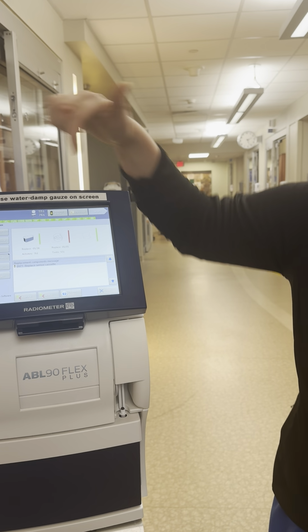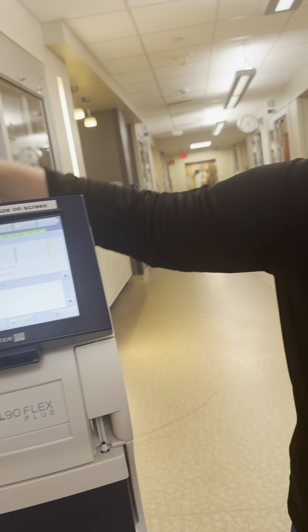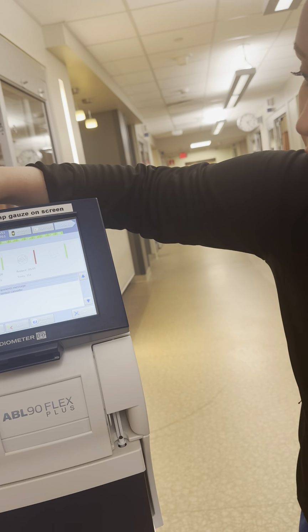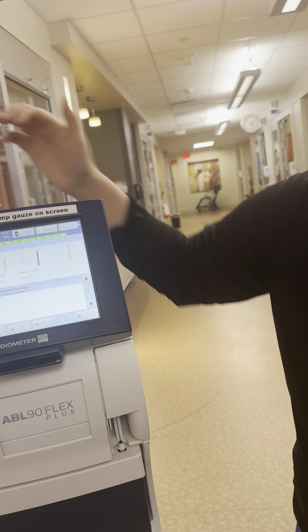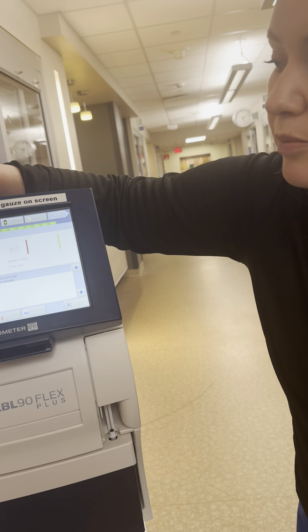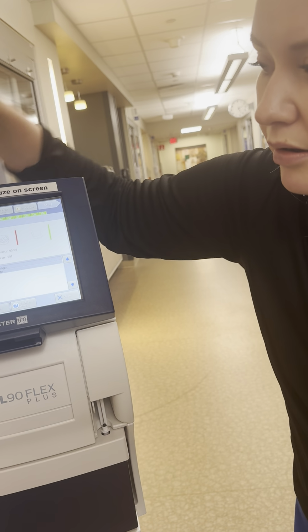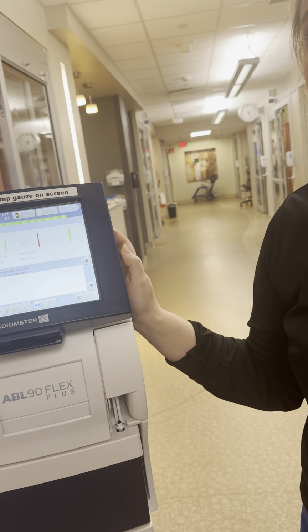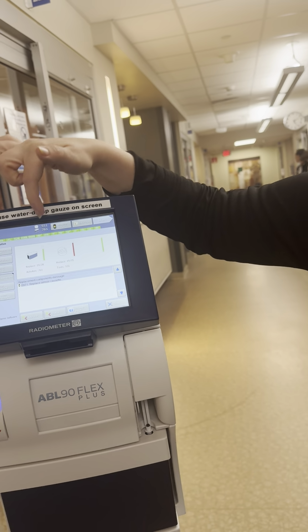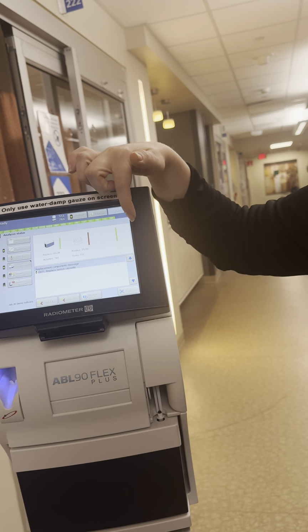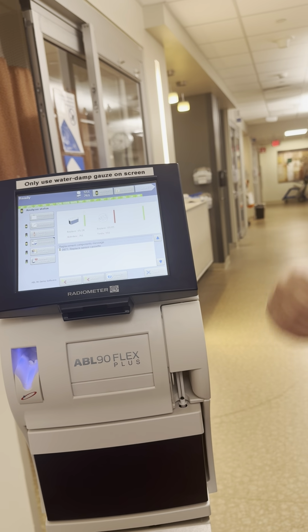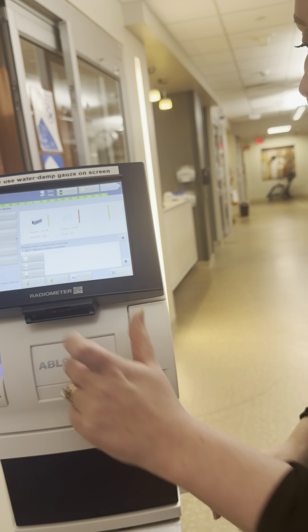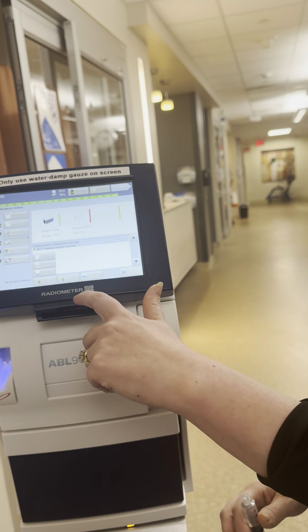But when you hit the stoplight, you're going to have individual stoplights beside anything that would need to be addressed. So your calibration, this is where we are in yellow because we're in demo mode. The main reason you're going to see that is if it's under consumables. These are all of your replaceable items. So this is your sample pack, this is your sensor cassette, and this is your paper. Anytime you are going to replace them, you hit the replace button, and you select which item it is that you're replacing.